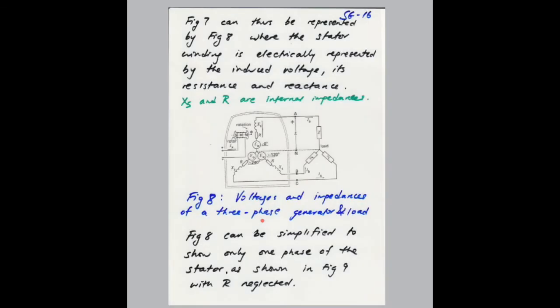If you look at the next slide, which is slide 16, we are now trying to represent the electrical effect of the machine onto the stator side. As we were discussing, the rotation of the rotor and the production of the flux in the air gap due to the rotor current induces three-phase voltages into the stator circuit, given by magnitude E0. If we take phase A as the reference, it will have an angle of 0. Phase B will have an angle of minus 120 degrees, and phase C will have minus 240 degrees.